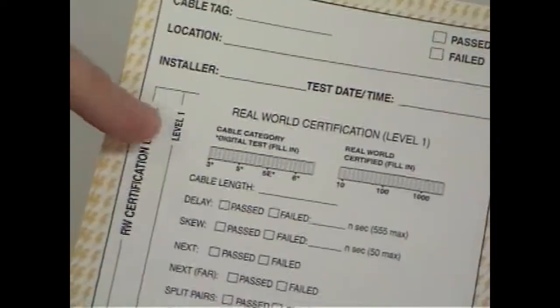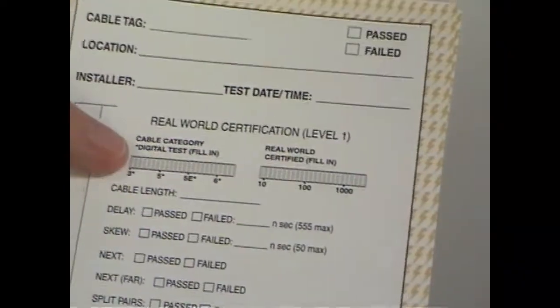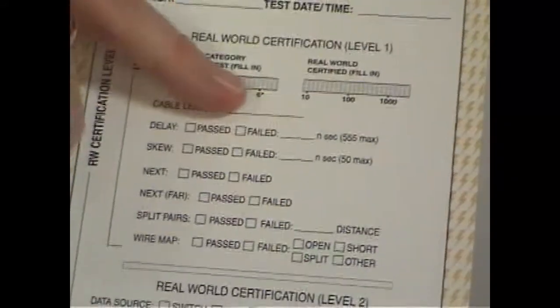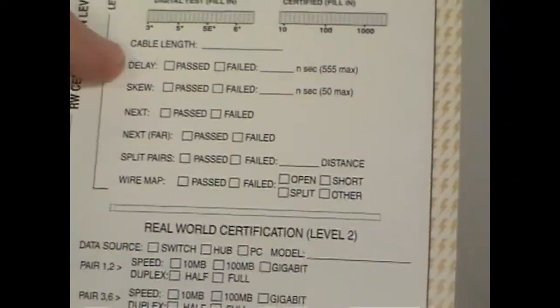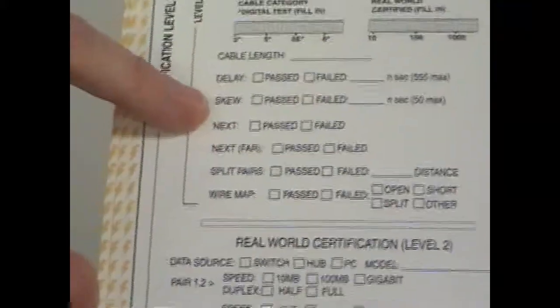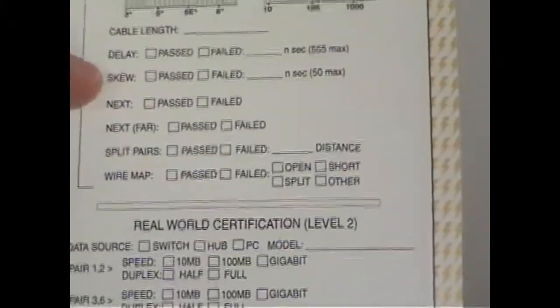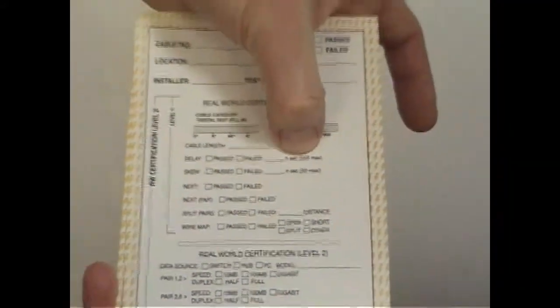Here you'd fill in cable category by filling in the graph, the predicted speed, the cable length, and here's where we're at now—the delay and the skew. The delay of the cable is 76 nanoseconds, and the tablet says you've got 555 to play with, so right away we know we have a pretty good cable.